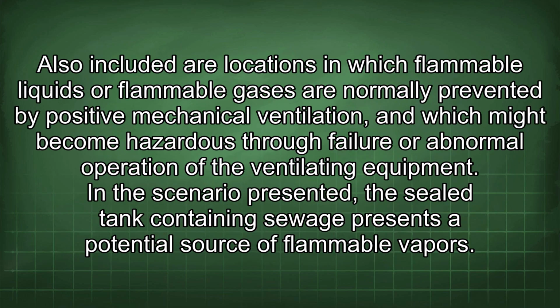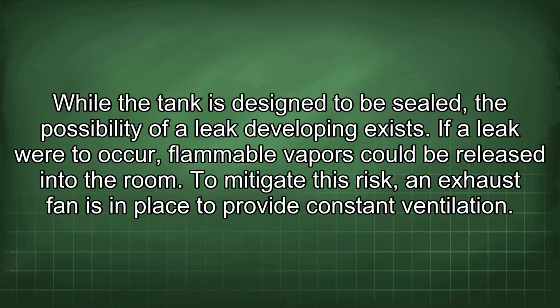Also included are locations in which flammable liquids or flammable gases are normally prevented by positive mechanical ventilation, and which might become hazardous through failure or abnormal operation of the ventilating equipment. In the scenario presented, the sealed tank containing sewage presents a potential source of flammable vapors. While the tank is designed to be sealed, the possibility of a leak developing exists. If a leak were to occur, flammable vapors could be released into the room.